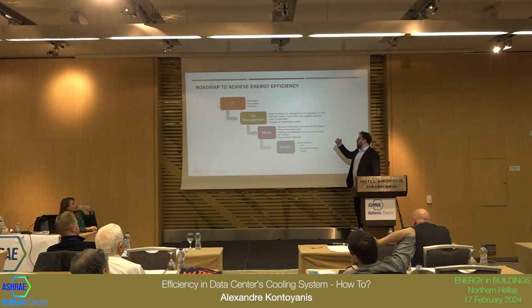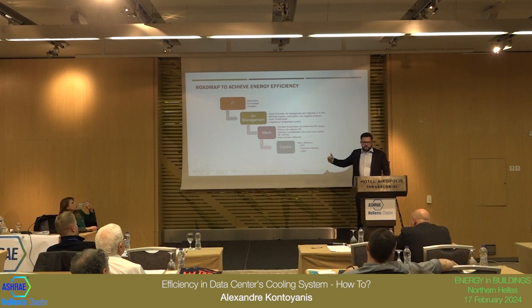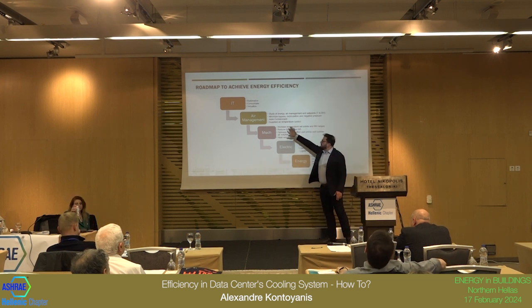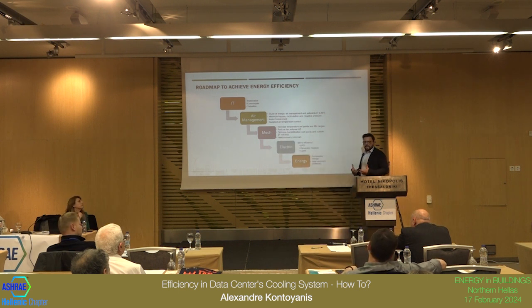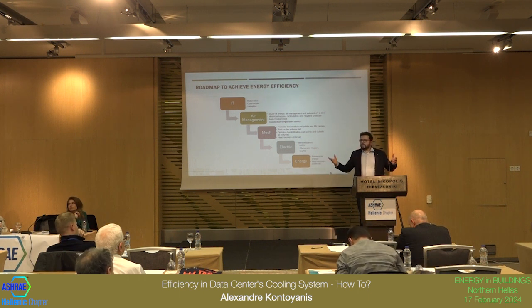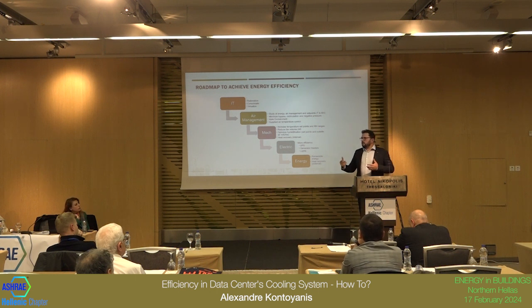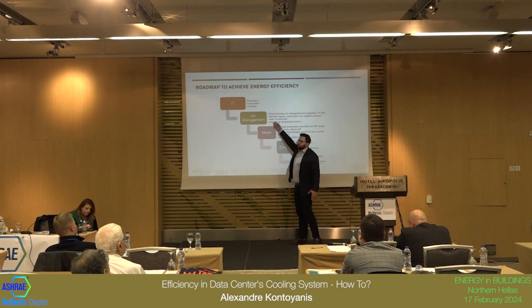Then we go to electric. Change our bulb lamps, change our UPS, generator heaters, for example, you can change it. And then you go to energy. So here, after we do all these steps, you know how much energy we need. Then you go to renewable energy and heat recovery. For example, in Canada, in Ontario, they need heat. So if you put in a heat exchanger and you start to heat the municipality water, they buy it. It's something that you are rejecting and you can start making money. But this is the last step. The low-hanging fruits are here.